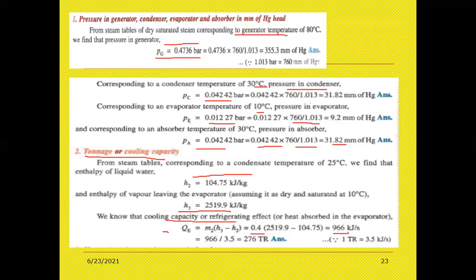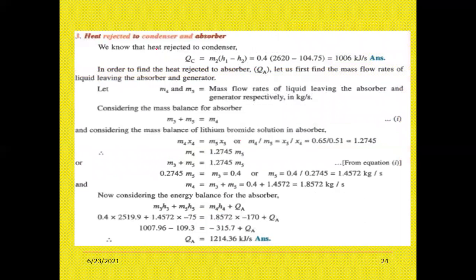966 divided by 3.5 is 276 tonnage. Now, the third one, heat rejection into the condenser. Heat rejection to the condenser and absorber. Therefore, the heat rejection to the condenser QC is equal to M2 of H1 minus H2. M2 is already given as 0.4. So 0.4 of H1 value minus H2 value. Therefore 1006 kilojoules per second.